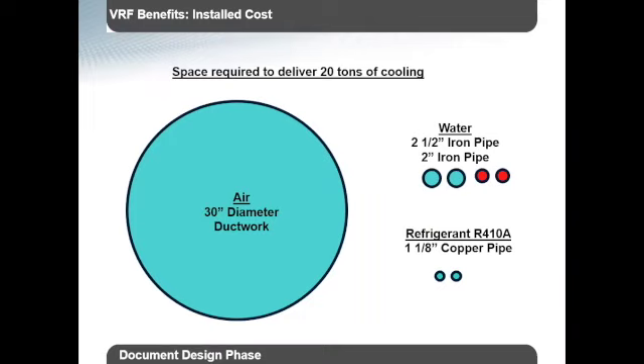If you're going with a hydronic system, you're going to have at least 4 pipes to provide heating and cooling. You're going to have your 2.5-inch iron and your 2-inch iron on the heating side. And then once you get all the way down to the VRF, you can see here on the bottom right, the largest piping that you're going to have on a VRF system is going to be 1 1/8-inch copper pipes coming from your outdoor unit to your indoor units. You can branch off of those directly. So you really save a lot of space, especially once we start looking into insulating the pipes.